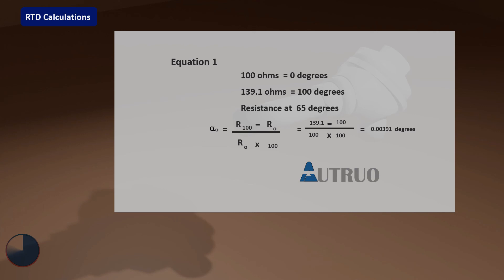Now that we have known our alpha temperature, we can calculate the resistance of the sensor at 65 degrees. The resistance at 0 degrees multiplied by the summation of 1 and alpha temperature multiplied by 65 degrees. Our resistance at 65 degrees equals 125.4 ohms.